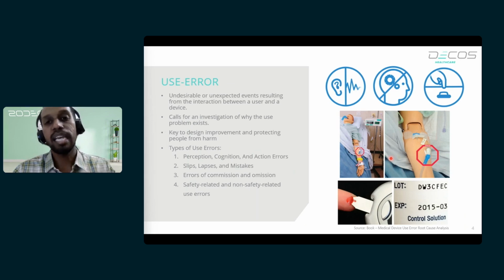So I need to take these into consideration, and whenever I'm going to design a medical device, I need to consider this at a very early stage in the device development itself, so that I can identify these user errors early and put a mitigation plan in the device design itself, so that the end prototype or the end device that is going to get into the market does not involve these user errors in real-time use.